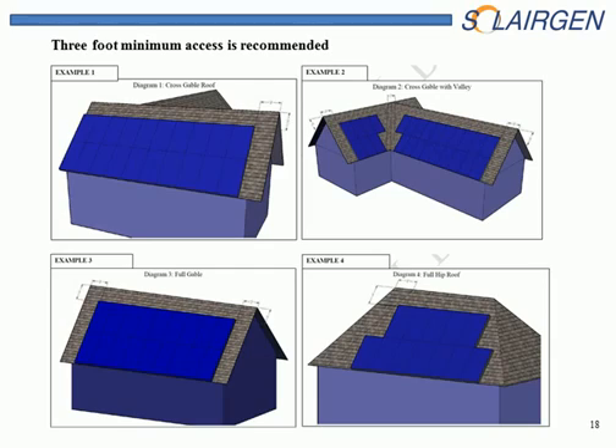As you can see with these examples, a 3-foot margin is maintained all the way around the roof. The one on the upper left is an exception, where you have the 3-foot margin to the right and the top, but the left-hand margin does not have that. You will see exceptions to this. You'll see where people have covered most of the roof. It may make it very difficult to access the roof, so this is recommended. It is not law in any state that I know of except for California.